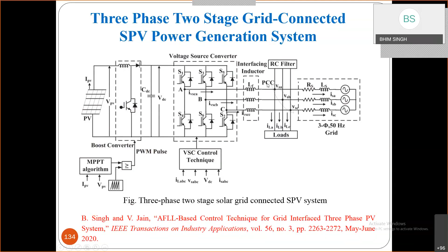Here, to compensate the load 24 hours, it works as a DSTATCOM apart from solar generation. And we modified the control with a power filter, so even when the voltage is distorted, and you can see an unbalanced load, the grid current is sinusoidal and not getting affected. You feed more power because the local load is not consuming that much, since the generation was constant.